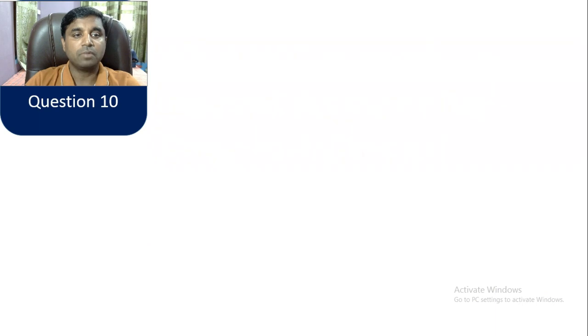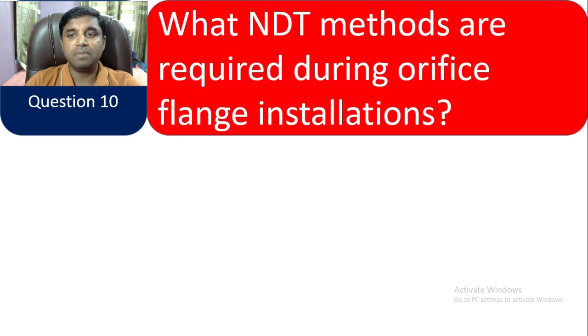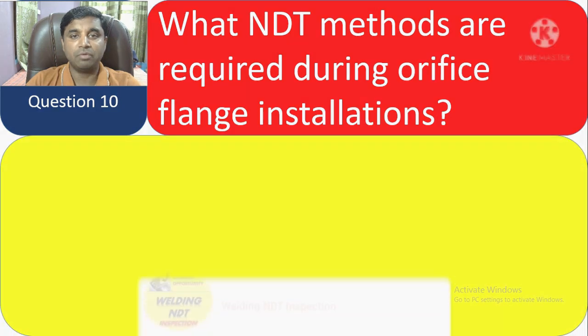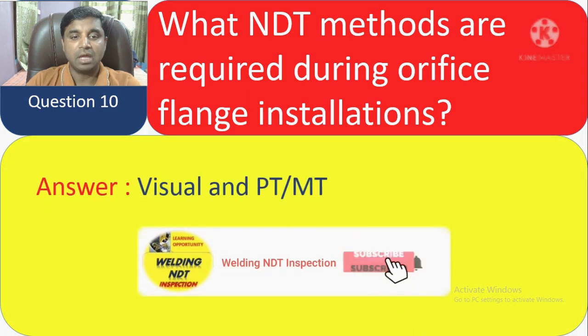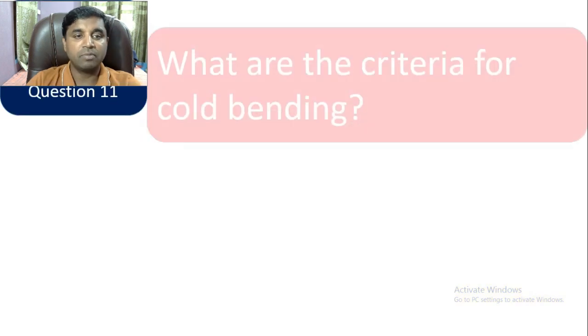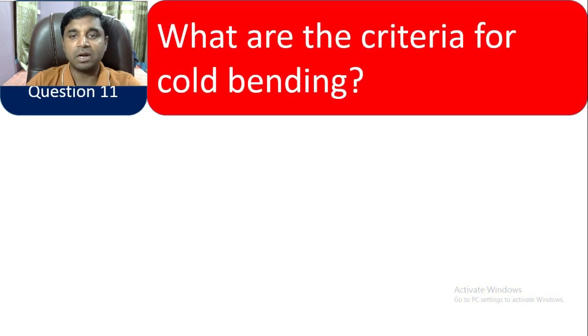Question 10: What NDT methods are required during orifice flange installation? The required methods are visual inspection and either PT (Penetrant Testing) or MT (Magnetic Testing). Visual inspection must be done, and then either PT or MT must be performed.